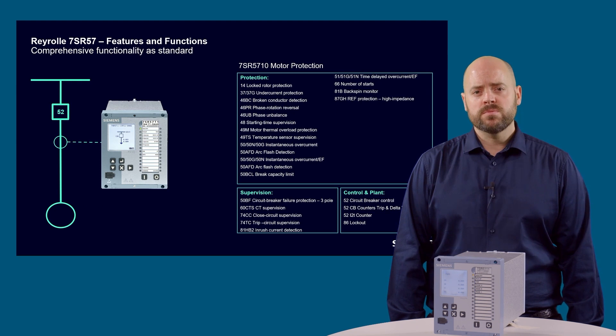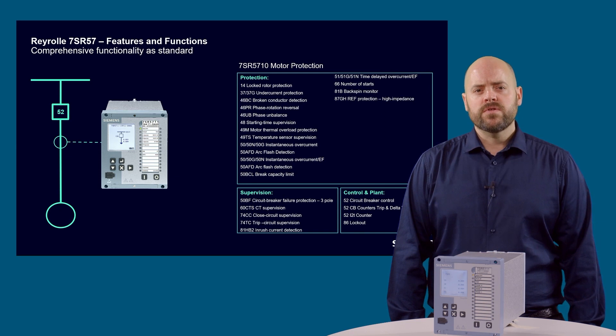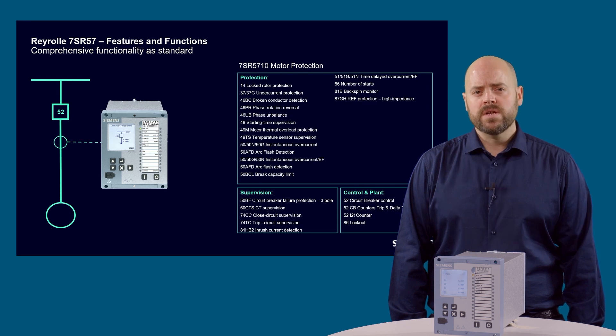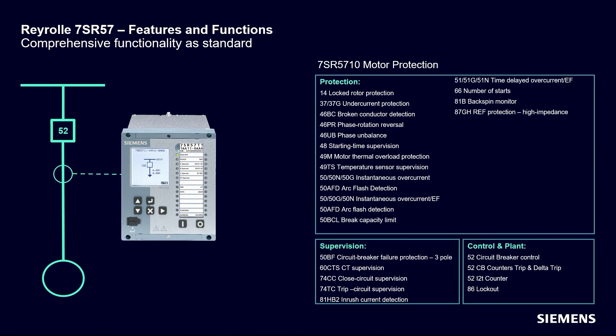Its 4CT inputs are suitable for connection to both 1A and 5A current transformer secondary windings and includes a core range of functions as standard. Operate curves of the thermal algorithm provided by function 49M take into account the effects of present loading, prior loading and unbalanced currents on the motor operating temperature. Starting and cooling constants modify the thermal characteristic during motor run-up and stopped conditions. A user-definable thermal curve is selectable to allow matching of the relay thermal characteristic to all motor and cooling system types.